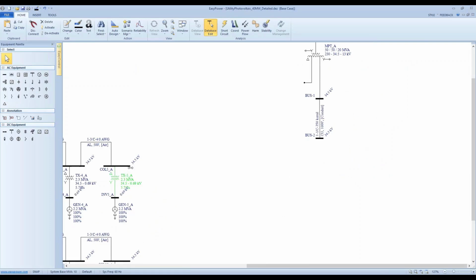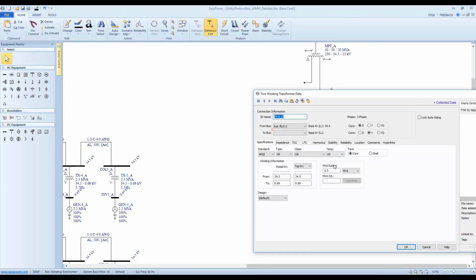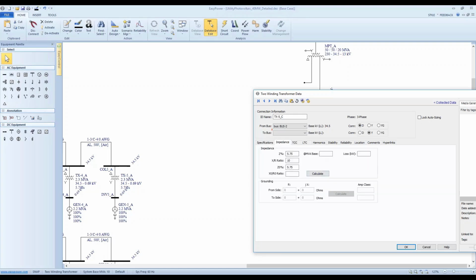Now let's go to the transformer. Like we said before, we can copy and paste the transformer here without changing the impedance. But what we need to do is to raise the MVA rating and MVA base by 20 times because we have 20 GSUs connecting in parallel, right? That's 46. This is 46 as well. Don't touch the impedance because they are consistent.